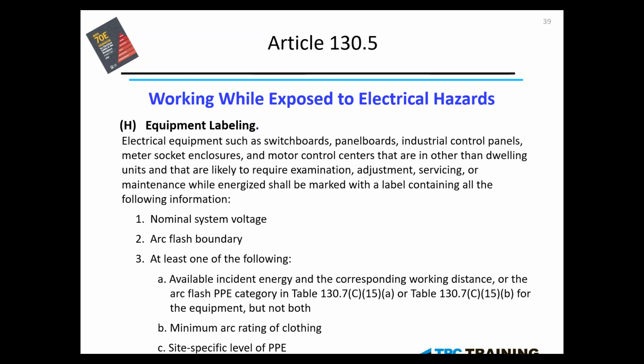shall be marked with a label containing all the following information: nominal system voltage, arc flash boundary, and at least one of the following: available incident energy or your PPE method, minimum arc rating of clothing, site-specific level of PPE, and so on. So as the analysis goes through, you'll see that it can get in great detail, but it is a requirement, even if there's a likelihood to require any of that interaction with that equipment.